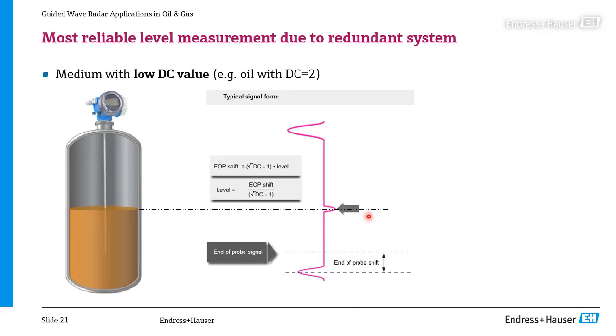But if you have oil on top, which has a low dielectric constant, what you will see, as you can see on the screen here as well, is that you get a small reflection back from the surface, because the dielectric change between air and oil is only 1 to 2, but you get a huge shift in the end of probe signal. And what the unit does, it compares the shift of the end of the probe with the level measurement, and it more or less compares the two to each other, so you have a backup system in case you have small reflections coming back from the oil itself or from a product which has a very low dielectric constant.